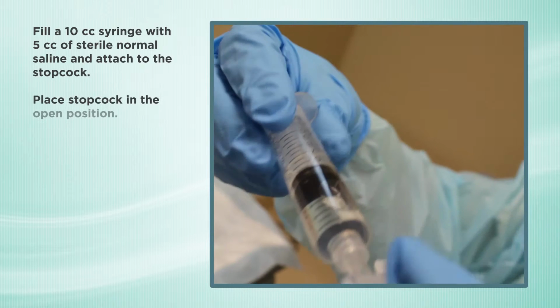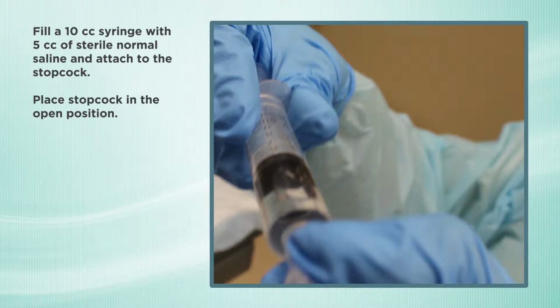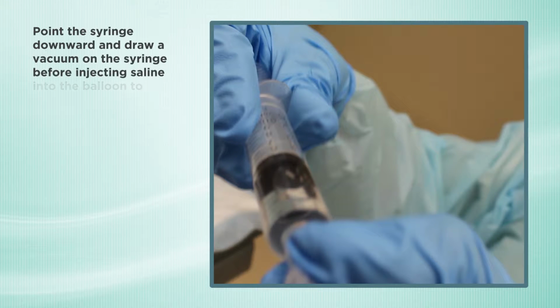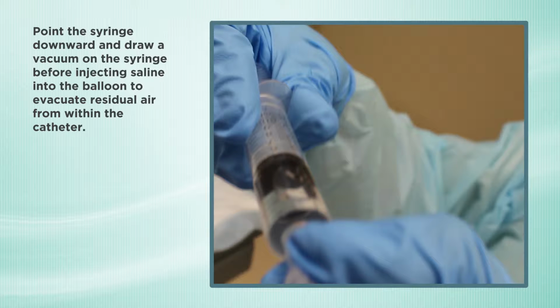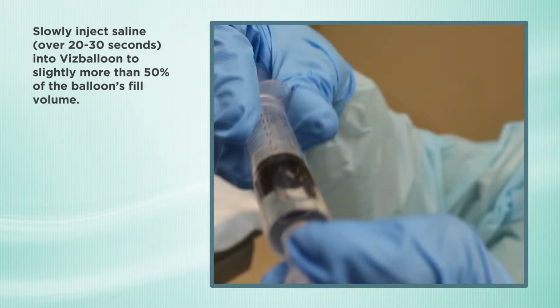Fill a 10 cc syringe with 5 cc of sterile normal saline and attach to the stopcock. Place stopcock in the open position. Point the syringe downward and draw a vacuum on the syringe before injecting saline into the balloon to evacuate residual air from within the catheter. Slowly inject saline over 20 to 30 seconds into Vizballoon to slightly more than 50% of the balloon's fill volume.